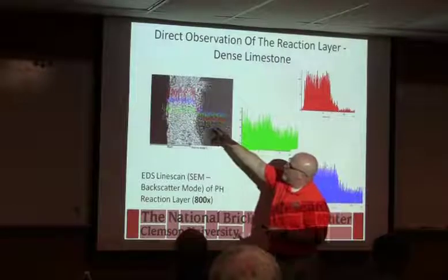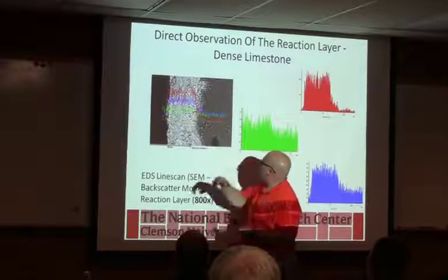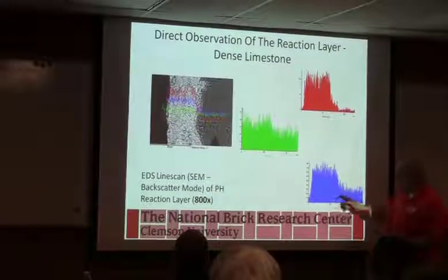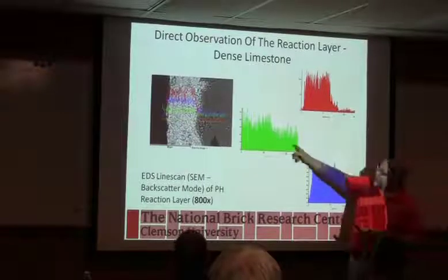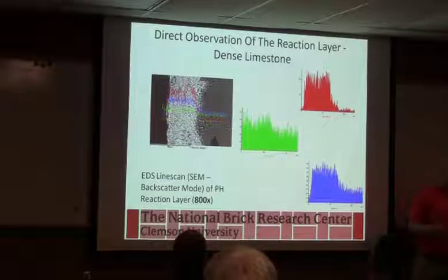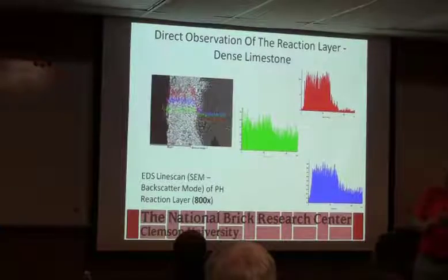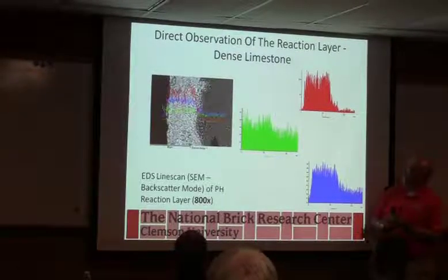It's overlaid over here, so you can see that bright, shiny layer has a lot of fluorine in it. It's got a little bit of sulfur in it, where it's picked up the sulfur, and then a very small amount of chlorine. So in order of preference, based on the studies we've done, it wants to pick up the sulfur first, and it will pick up sulfur on any fresh surface it can.